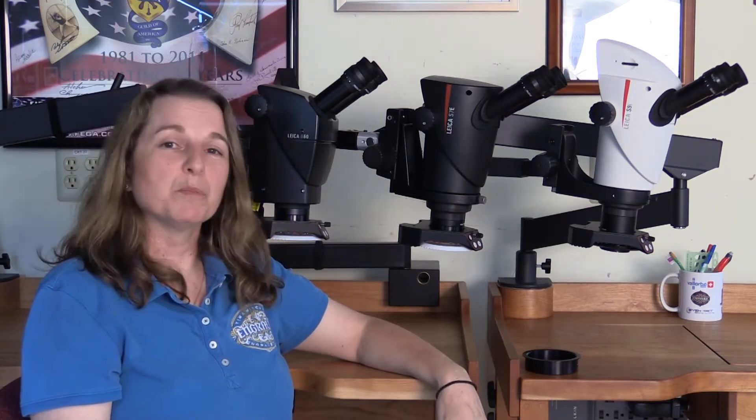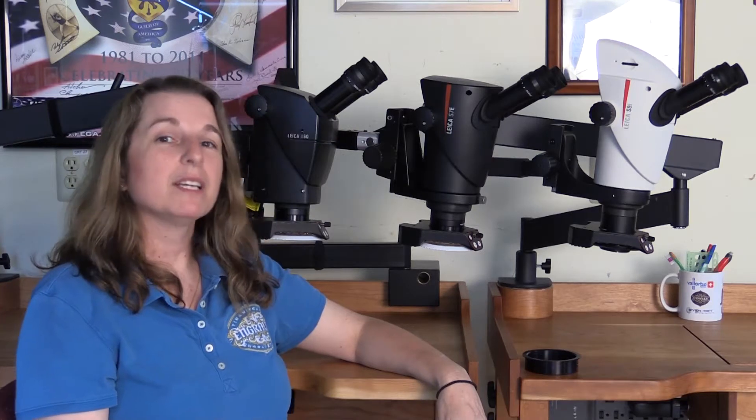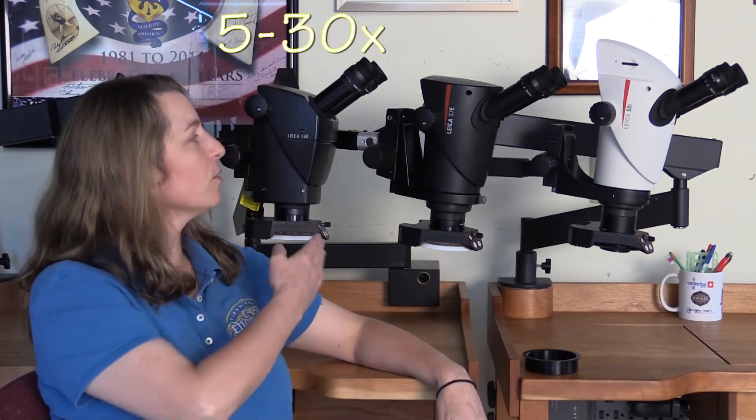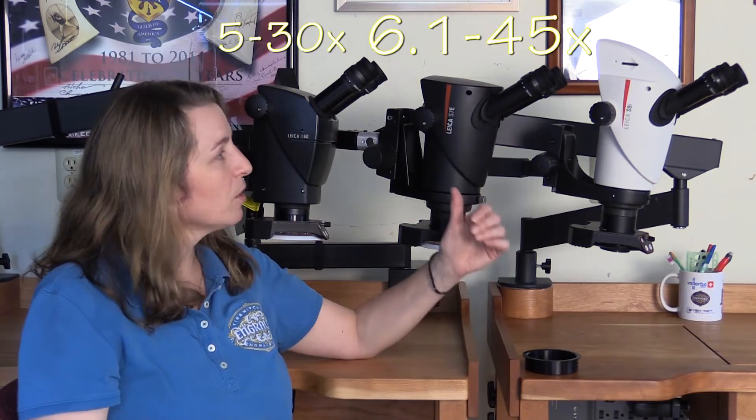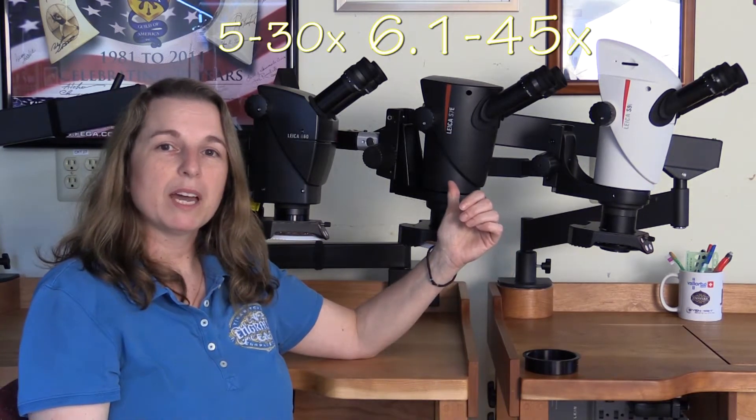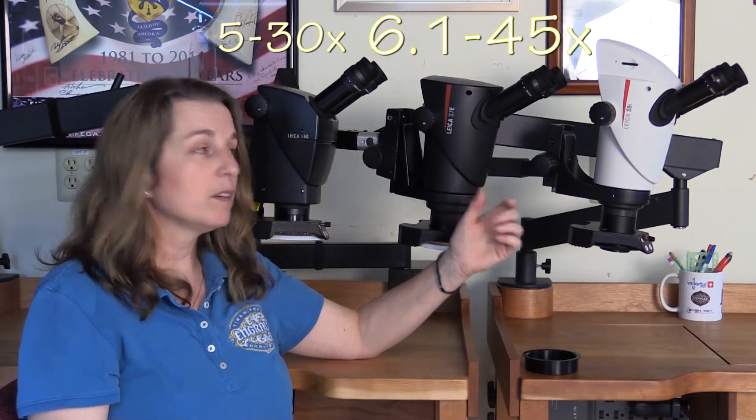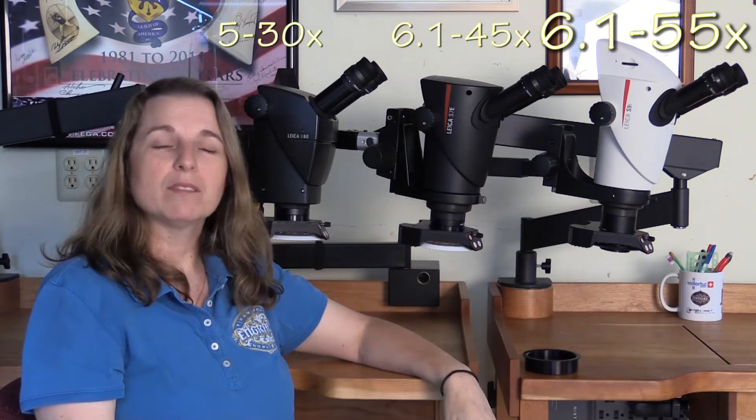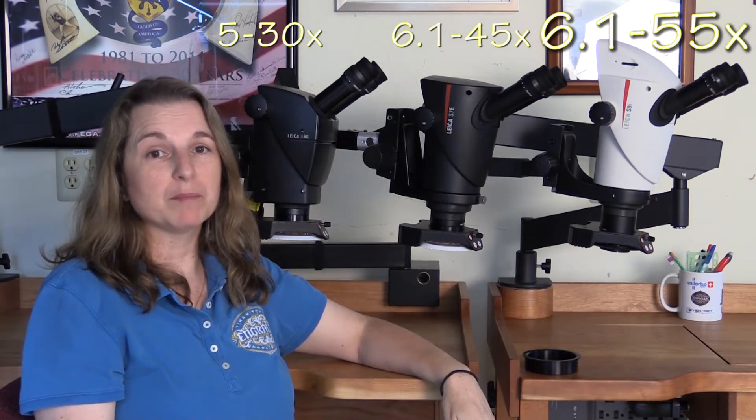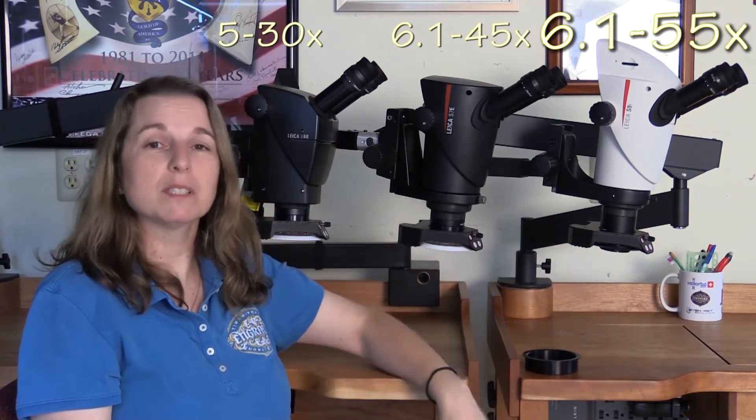Some of the differences between these scopes are in magnification. For the A60 we have 5 to 30, for the S7 we have 6.1 to 45, and for the S9 we have 6.1 to 55 times. So quite a bit of difference in magnification.